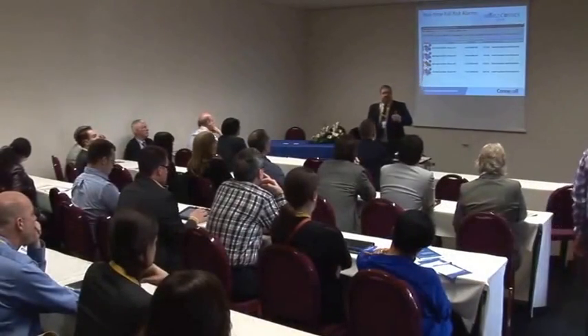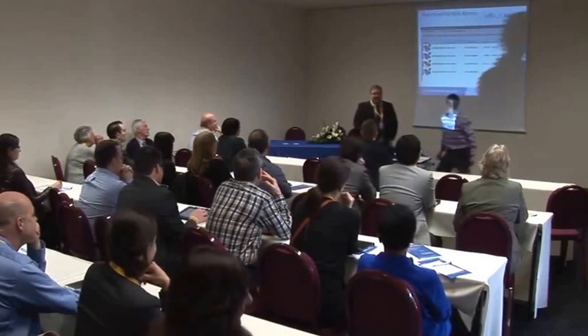Here's an example of the active alarm screen. This snippet live from a site shows high-risk patients who are out of compliance. The notification says 'bed exit armed' — meaning the clinician set up the bed but did not yet enable the bed exit alarm. As soon as they go back to the room and enable bed exit on the main panel, the alarm is removed because the bed is back in compliance.